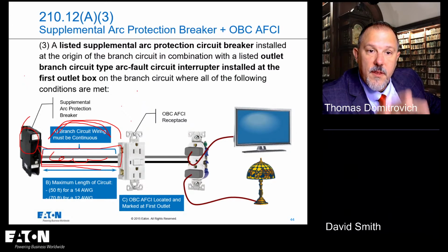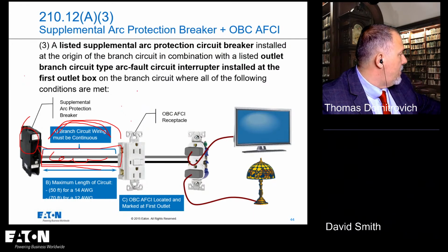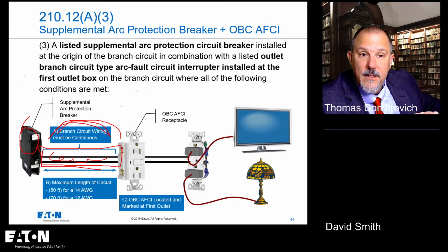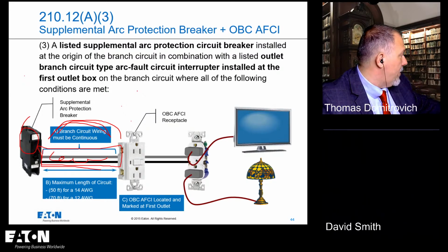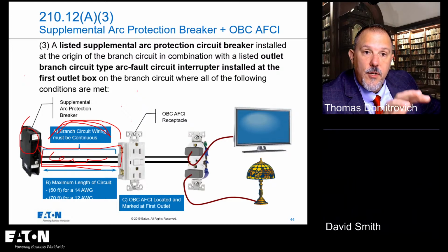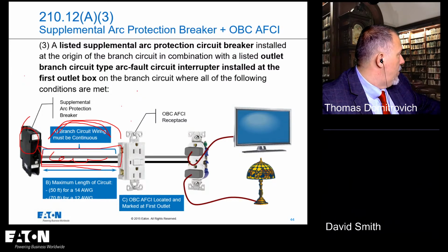So we put this one in, and we said a listed supplemental arc protection breaker, but no standard exists to be able to make a listed supplemental arc protection circuit breaker. So we have no solution for this scenario.